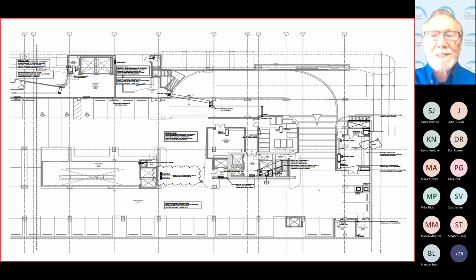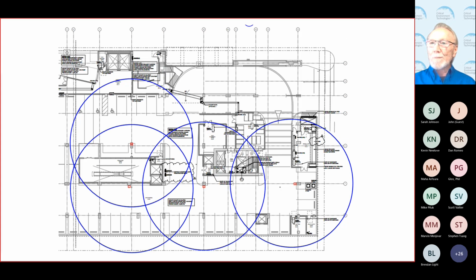As I mentioned, these sensors work on the premise of natural diffusion and convection, let alone any other introduction of movement of the ambient atmosphere around them. If you can have those sensors in towards the area that they're monitoring, as opposed to on the perimeter walls, then you're going to get 360 degrees of diffusion and convection and ambient atmosphere movement around them. So they're going to have a much greater radius of coverage.